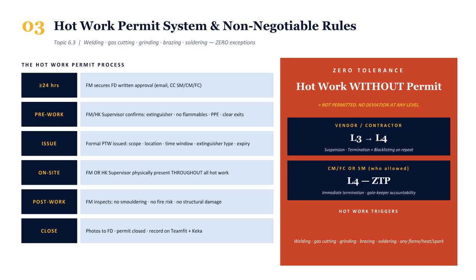First, 24 hours before any hot work, the FM must secure written FD approval by email with SM, CM and FC copied. Second, immediately before work, the FM or HK supervisor confirms 4 pre-work conditions: extinguisher in place, no flammables within 5 meters, vendor PPE complete, exits clear. Third, a formal permit to work is issued: scope, location, exact time window, assigned extinguisher type, and an expiry time.